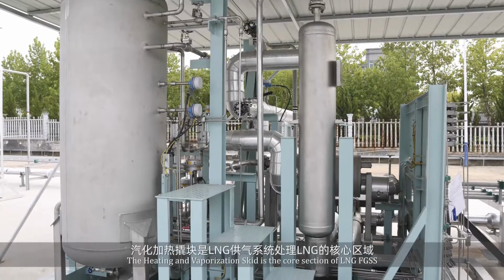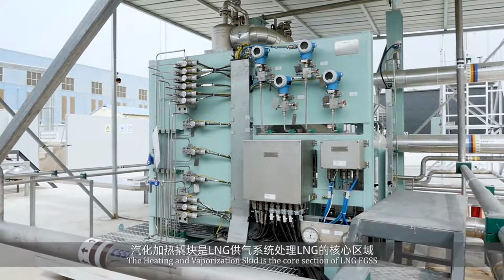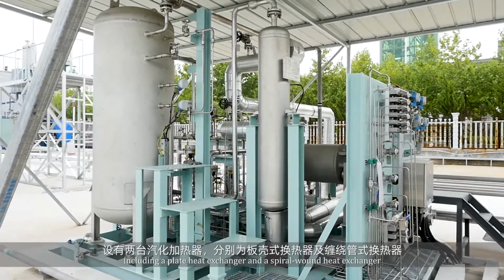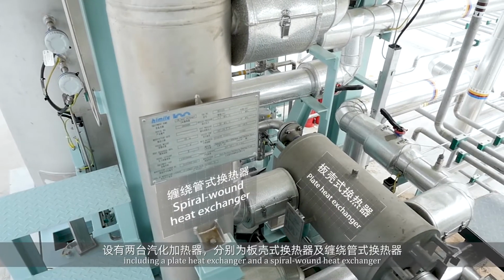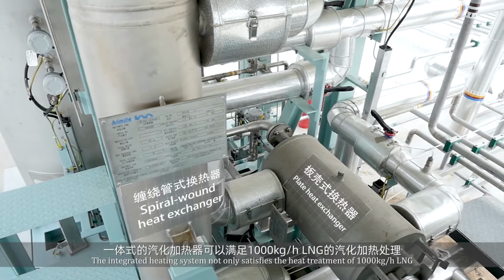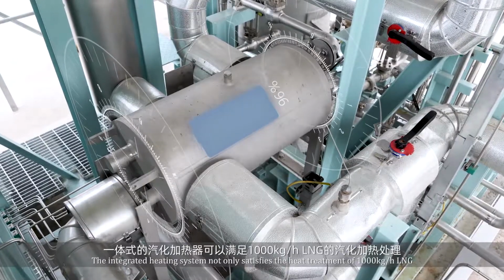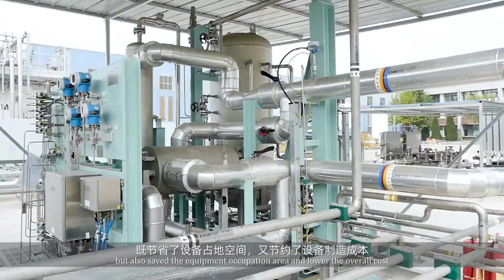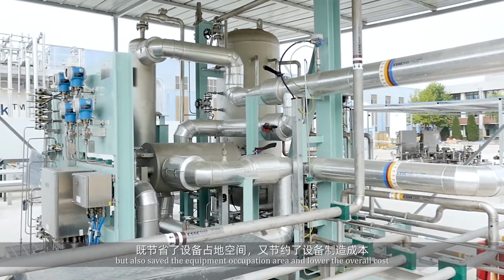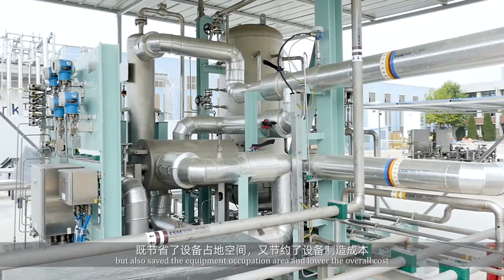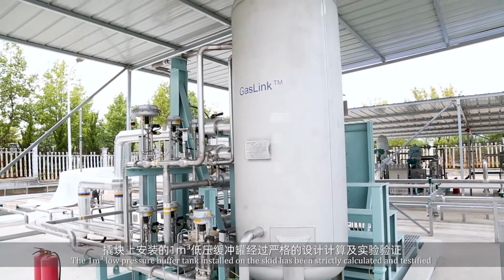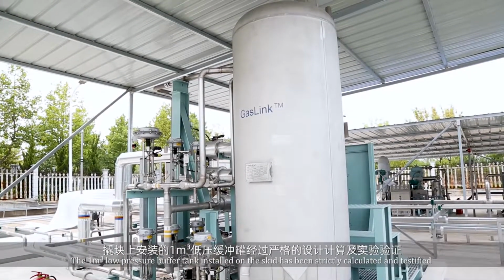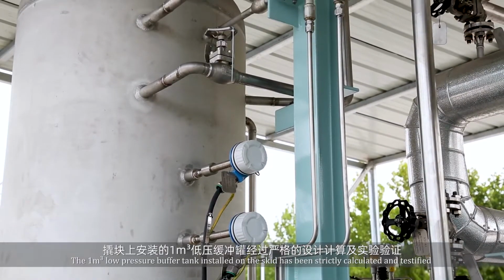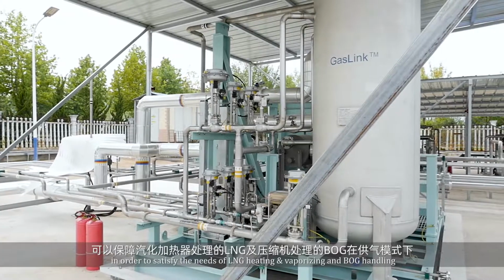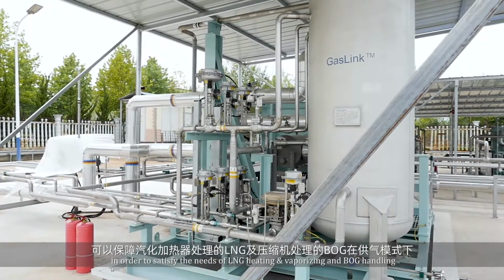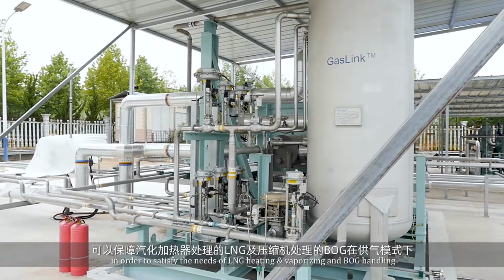The heating and vaporization skid is the core section of LNG FGSS, including a plate heat exchanger and a spiral-wound heat exchanger. The integrated heating system not only satisfies the heat treatment of 1,000 kilograms per hour LNG, but also saves equipment occupation area and lowers the overall cost.